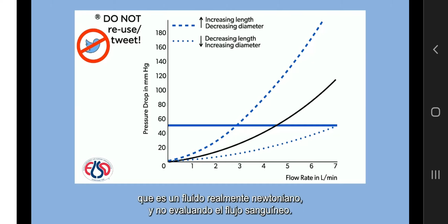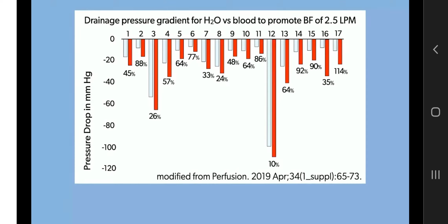This study investigated blood flow through various ECMO cannulae. Independently from the cannula, the flow was lower at any given pressure gradient pumping blood compared with the charts presented by the manufacturers. A variable fractional additional pressure could be needed for blood compared with water. So the published chart does not correspond to clinical performance and may not provide the best guidance at the bedside.